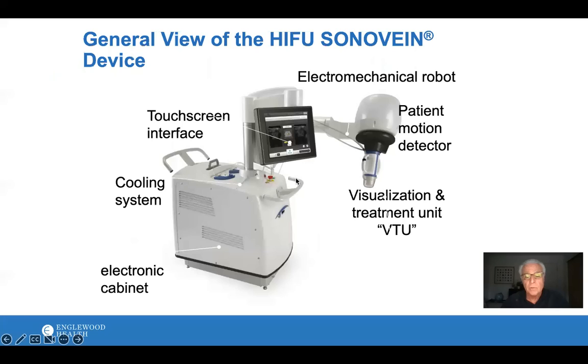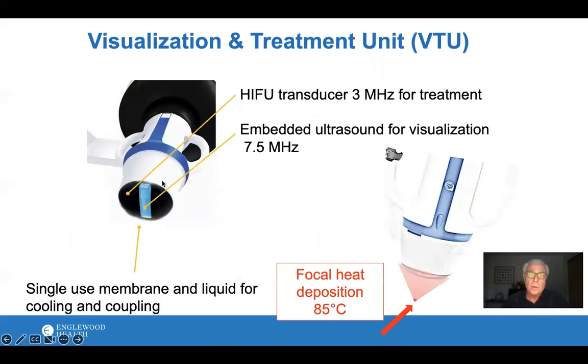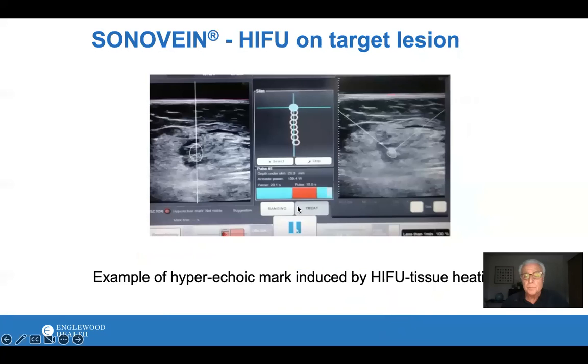This is the SonoVein unit itself — a touchscreen that you control things with, and the working unit is at the bottom. It has a regular ultrasound probe and a 7.5 megahertz probe to visualize the target vein. There's also the HIFU transducer, which delivers a concentric, focused cone of energy that heats the tissue to about 85 degrees Celsius. You can see the tissue thicken right after targeting, so you know you've destroyed it.